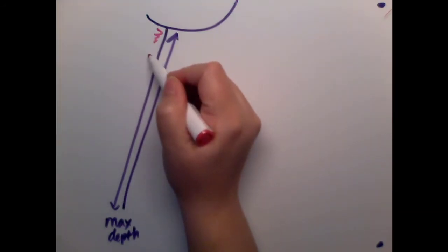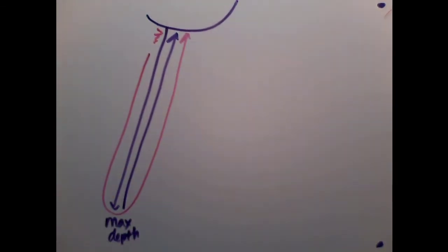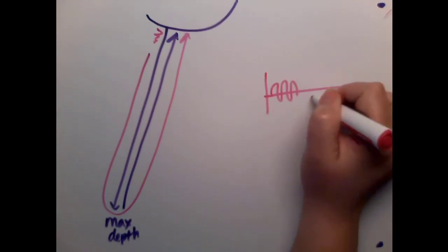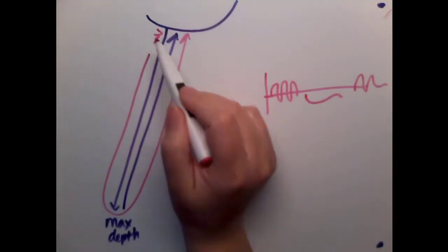Most of our time is that off time, waiting for the sound to come down and back up to the transducer. Remember when we were graphing that out, we had our pulse and then that space, that off time, and then the pulse again. The pulse is this, and the off time is all of this listening time that we're waiting for. So it makes sense that our 13 microsecond rule, or the range equation, helps to explain how long that time is going to take.